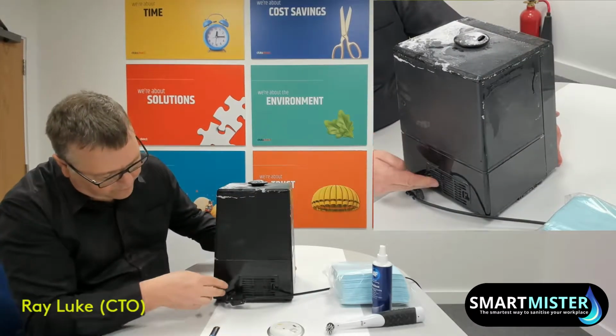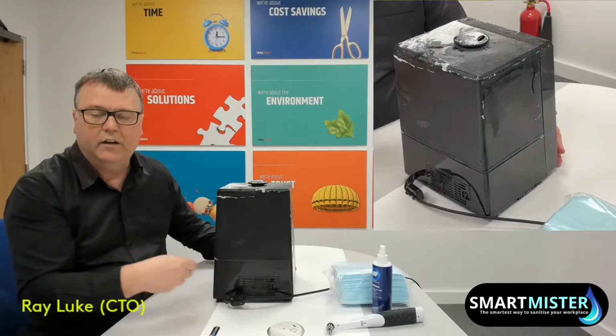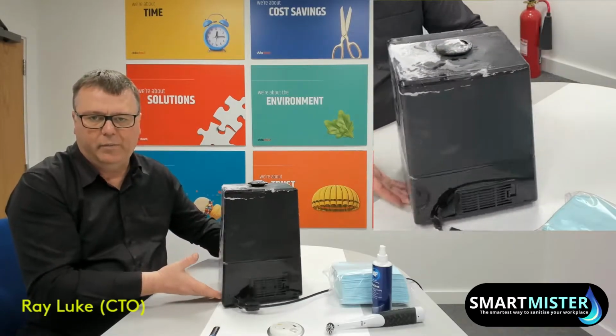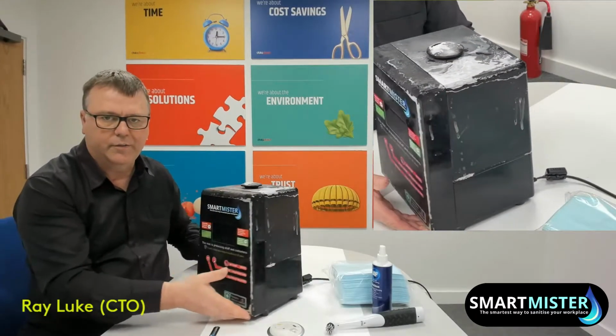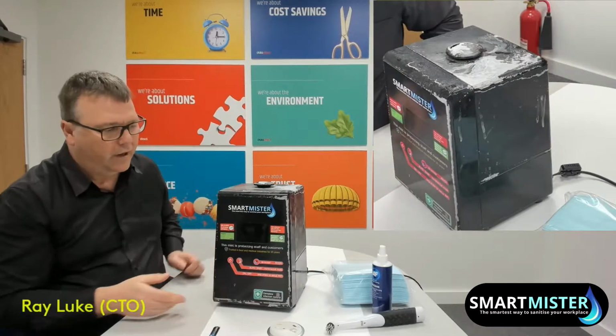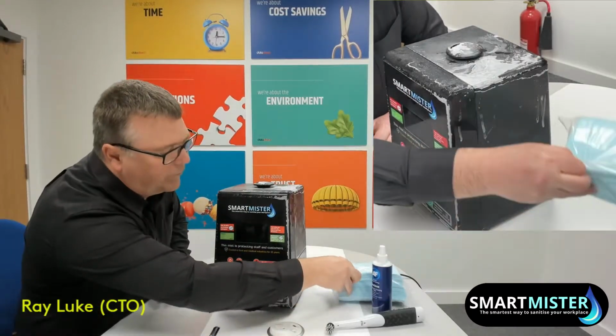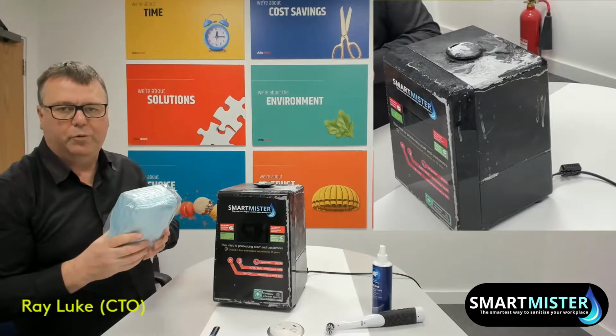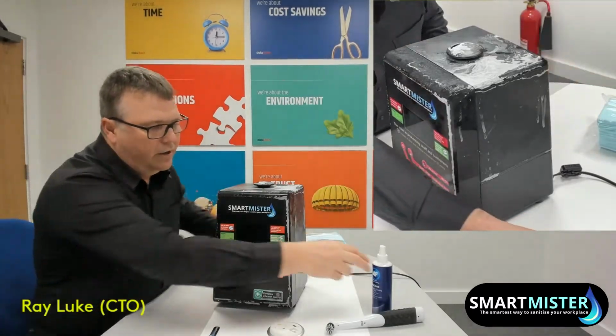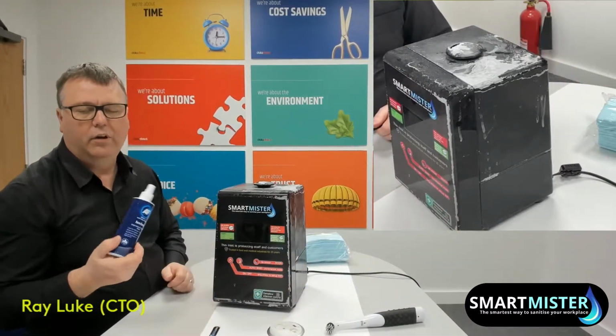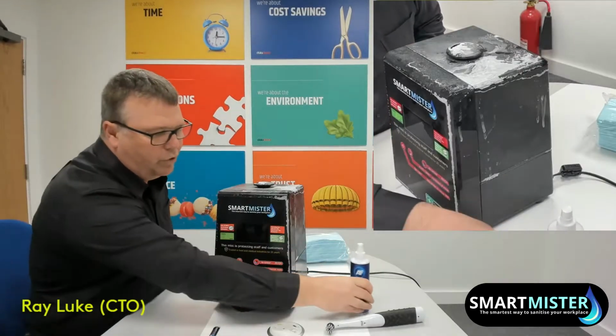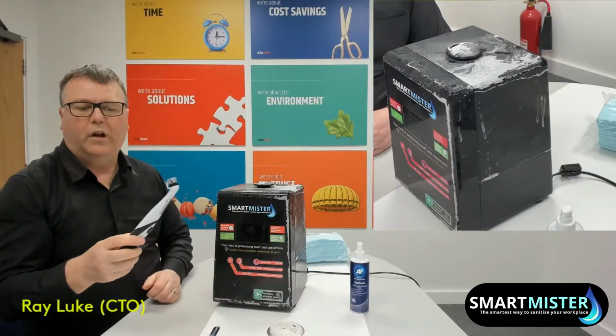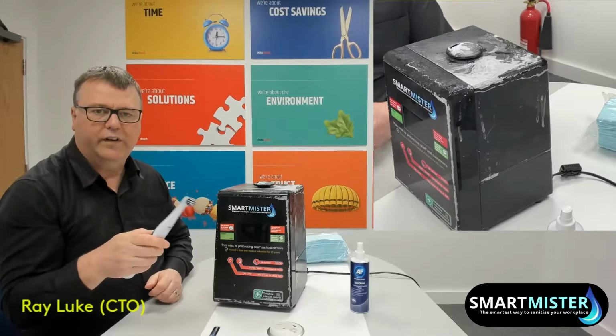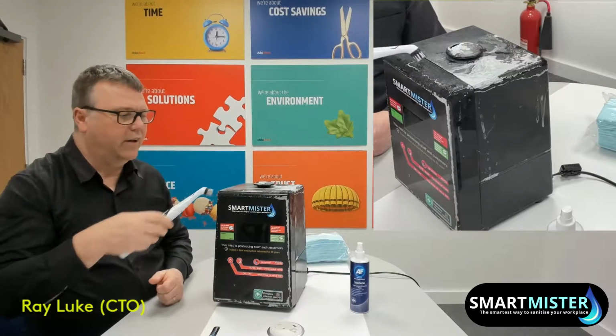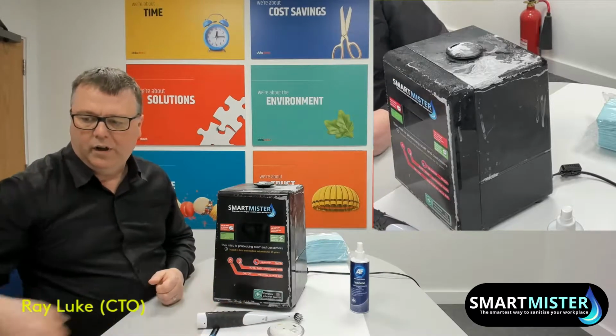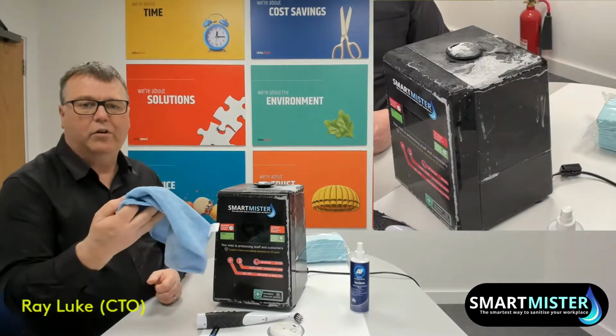The filter in the back is clean and that generally doesn't get affected by salt, but the rest of the machine does. To clean it you need some lint-free cloths, which we have in the cleaning kit, some isopropyl alcohol, white vinegar we use a bit, and then an ultrasonic wand - effectively a big toothbrush - to agitate any salt crystals and break it up, plus a microfiber cloth.